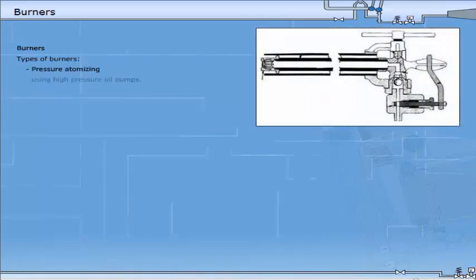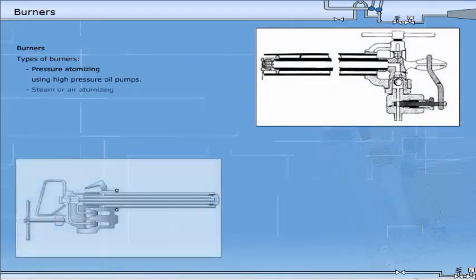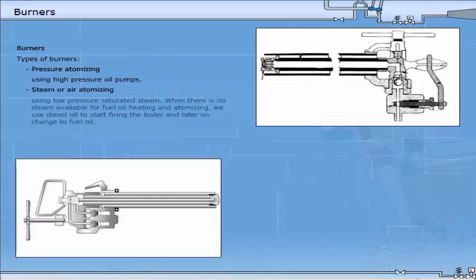Pressure atomising using high pressure oil pumps. Steam or air atomising using low pressure saturated steam. When there is no steam available for fuel oil heating and atomising, we use diesel oil to start firing the boiler and later on change to fuel oil.